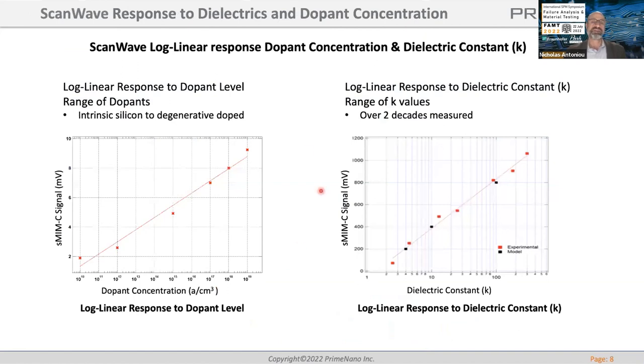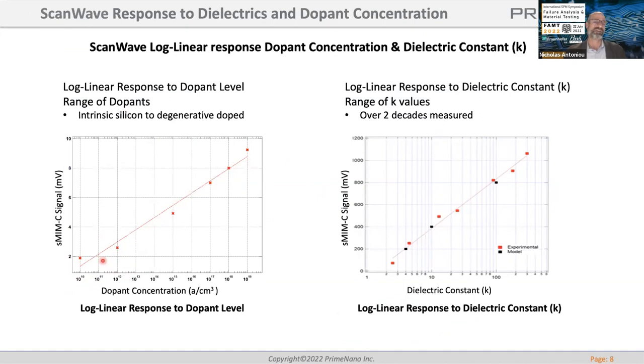Let's look at the response of the sMIM signal to dopant concentration. We made samples because we couldn't find off-the-shelf very low-doped or intrinsically doped silicon, so we had samples made with very low doping and intrinsic silicon to measure the response down to that level. We also have a sample going up to 1E20. The response is log-linear, meaning it's easy to predict a value if you have at least a couple of points on this curve from a reference.